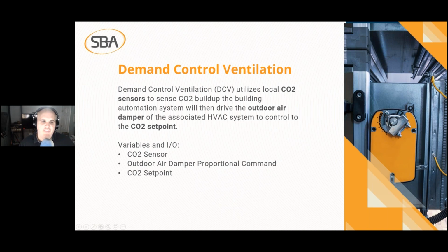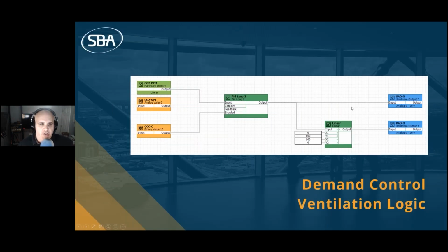And then you will have your CO2 set point, and that CO2 set point is what we drive towards. Now, here's some code I wrote up this morning. You'll see the approach. You've got a PID loop, and an occupancy command enabling the PID loop, which I always recommend: enable your PID loops based on occupancy or state, so you have stateful loops and they don't wind up and wind down. And you've got CO2 coming in, you've got your set point, and then you have a linear inverter. Some will call this a scalar object, some will call it a reverse or a negate object.